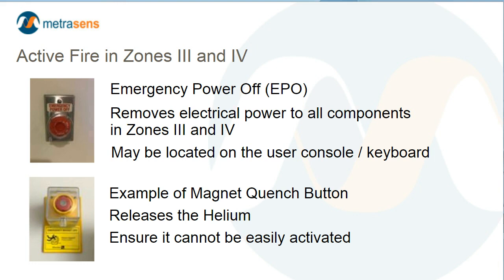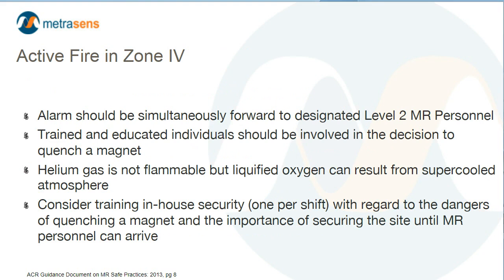The ACR recommends that when a fire alarm or any other emergency alarm occurs, it be forwarded to designated Level 2 MR personnel to allow them to respond and assist in maintaining control of the MRI environment. With regard to a quench, only designated and trained individuals should be involved in the decision to quench a magnet, particularly in the event of an active fire in MRI.